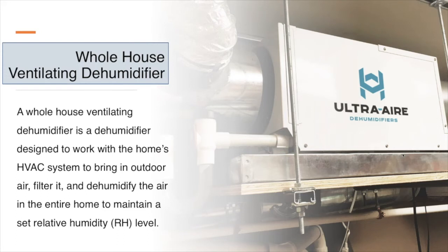And then we have a whole house ventilating dehumidifier, and these integrate with the HVAC system, and we're going to discuss some installs here. But again, we are going to dehumidify the living space based on a set RH point. So let the air conditioner come on and get to that sensible, that temperature set point on the thermostat. When it shuts off and the relative humidity is still too high in the space, then the dehumidifier can come on. And the dehumidifier is really going to shine in the shoulder seasons where we're not running a lot of AC.